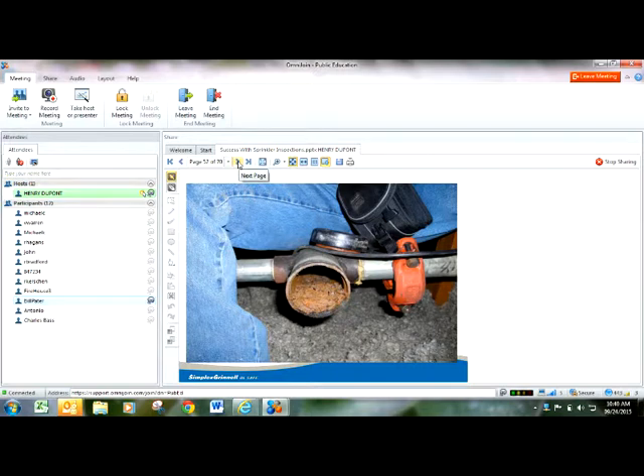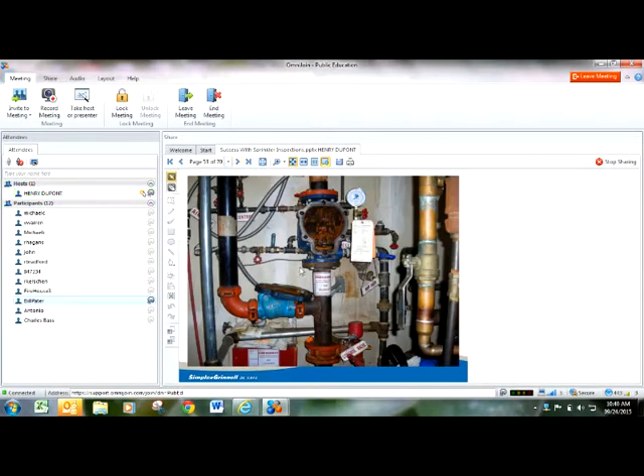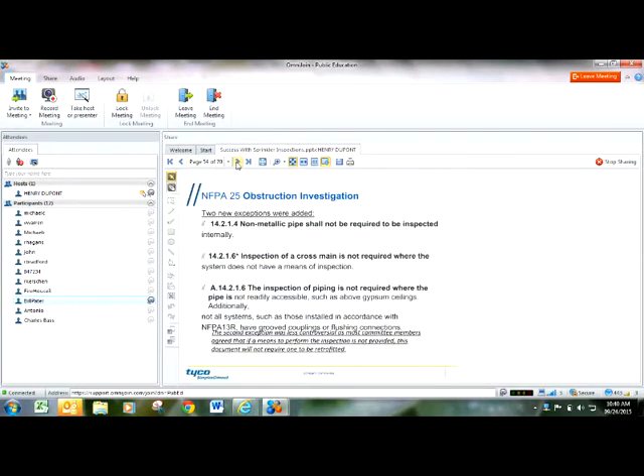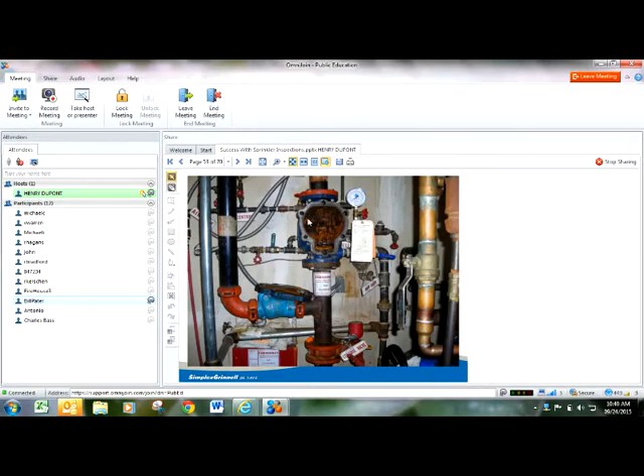So microbiologically influenced corrosion is a very common thing out there nowadays. We're seeing a lot of it. This is the inside face of a dry pipe sprinkler valve, and that stuff is growing inside of there too. If we find the presence of this, what we like to recommend is a water analysis. So we'll take a sample of the water out of the sprinkler system.